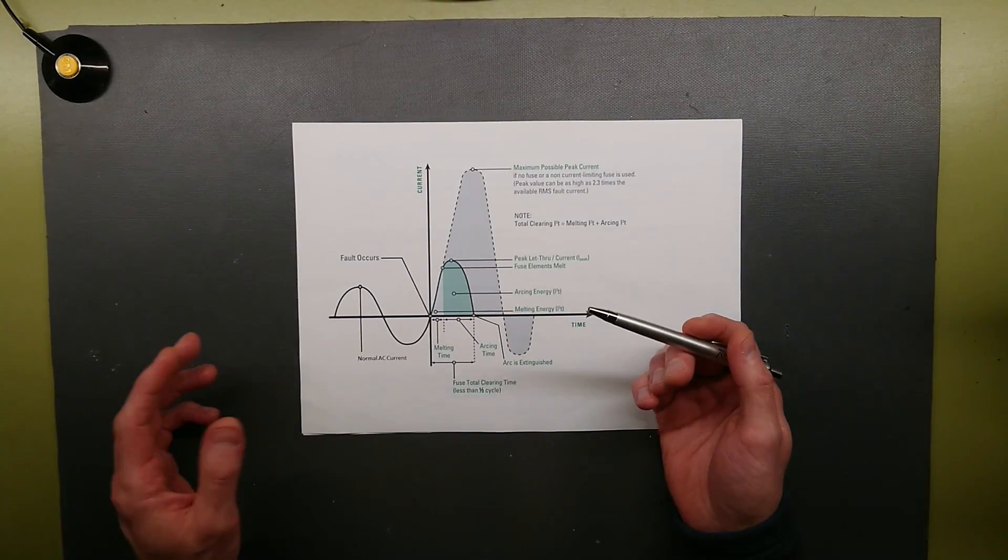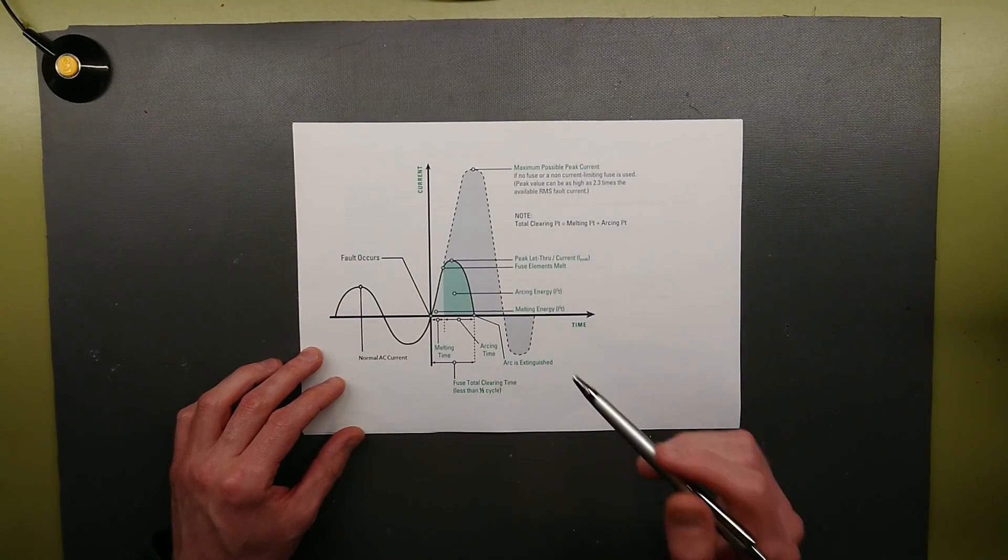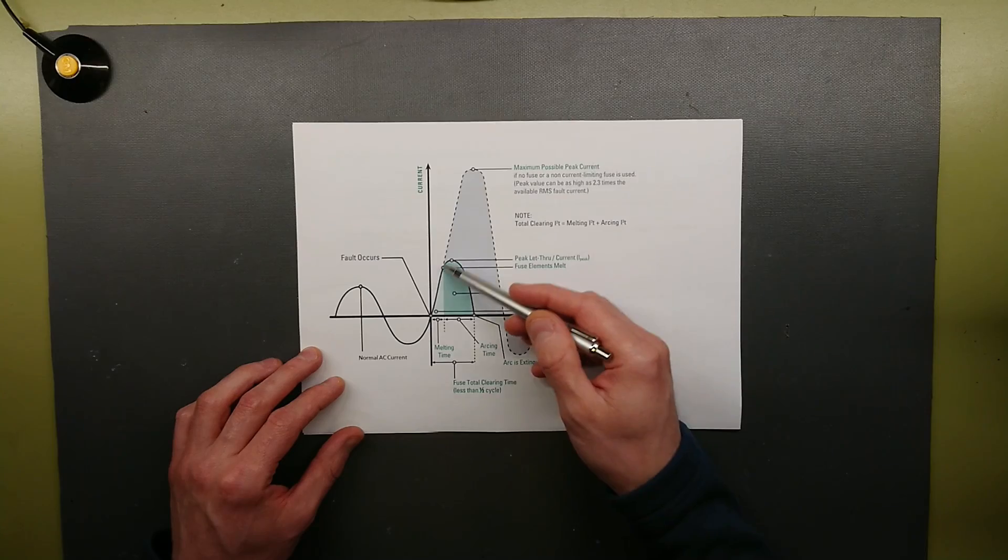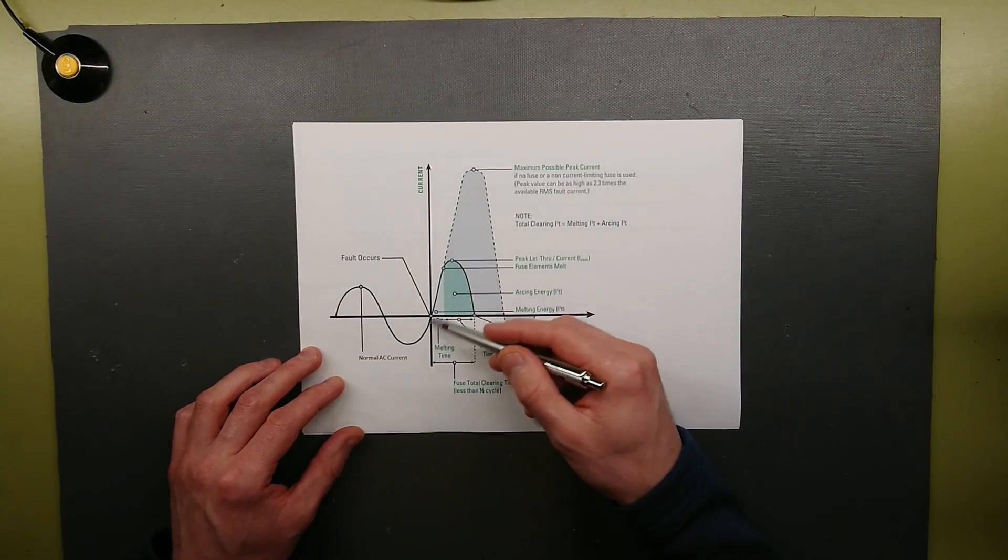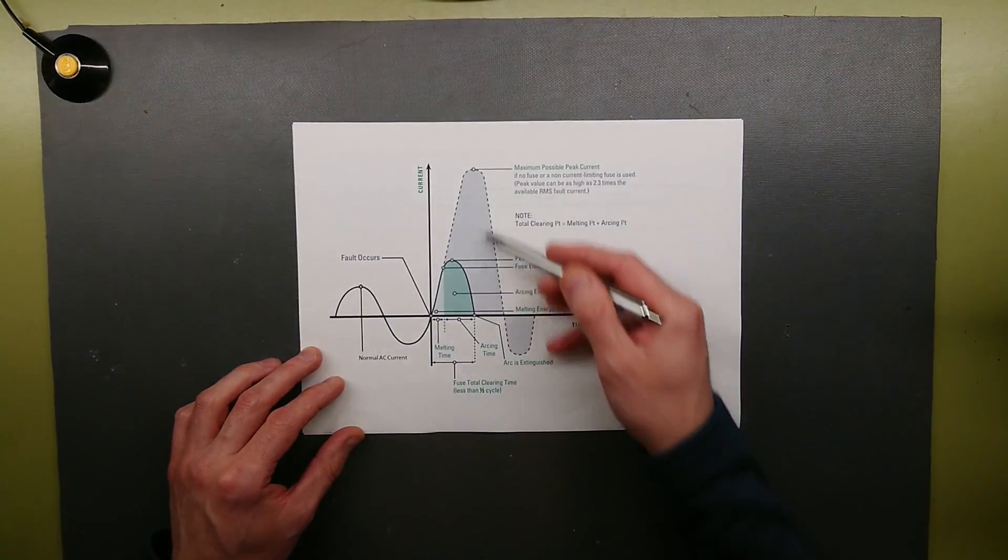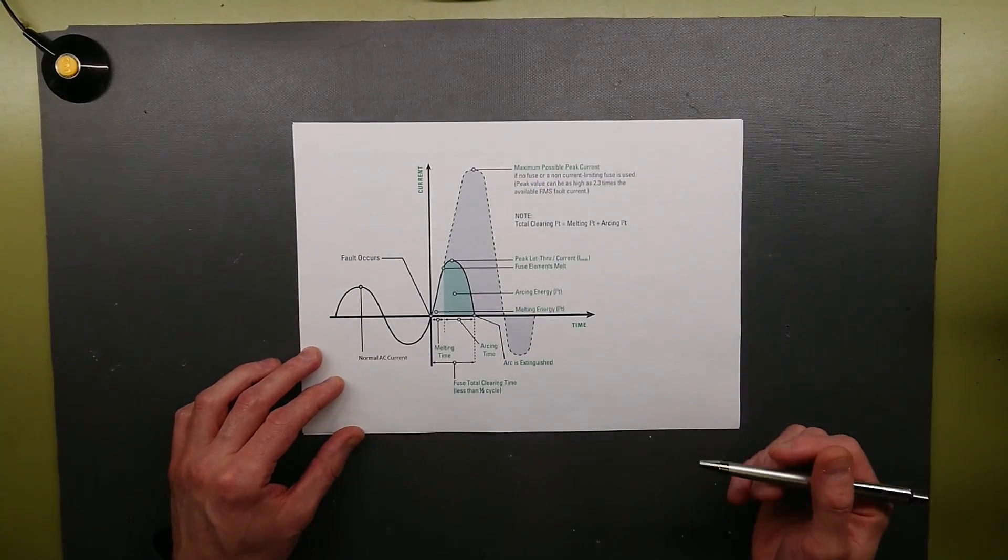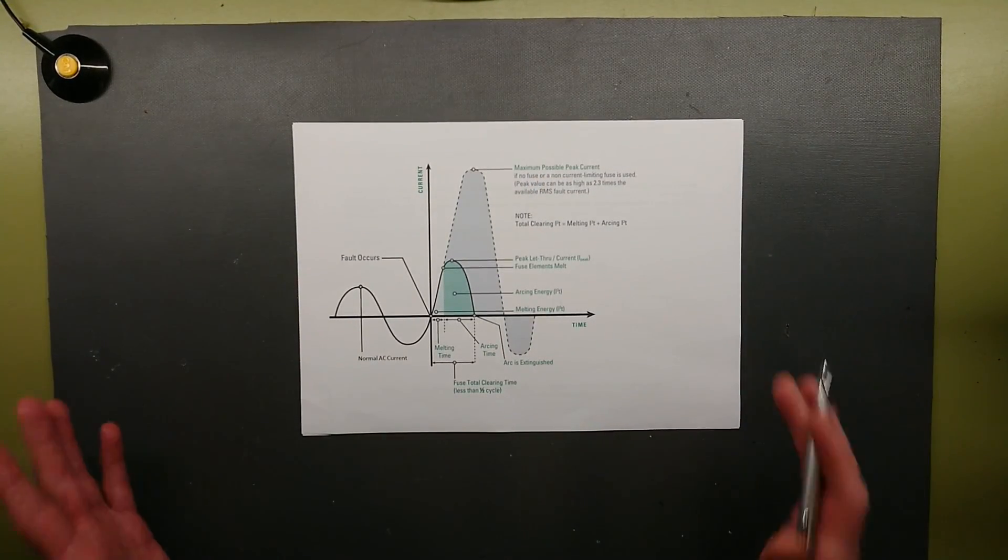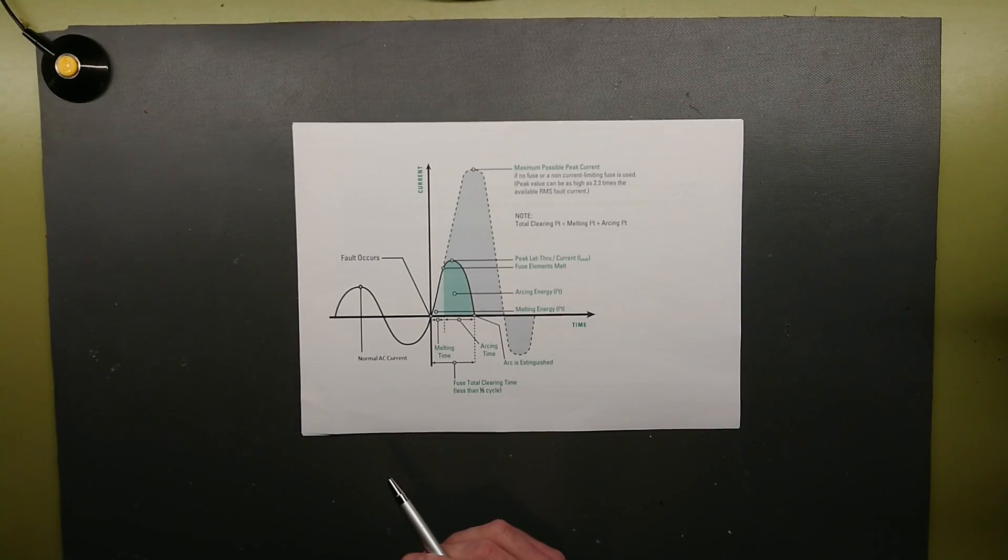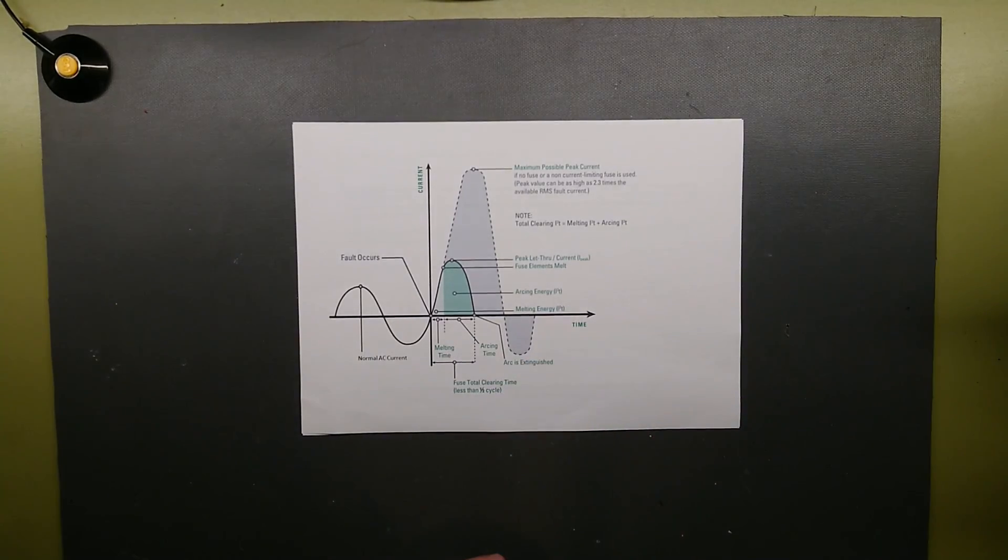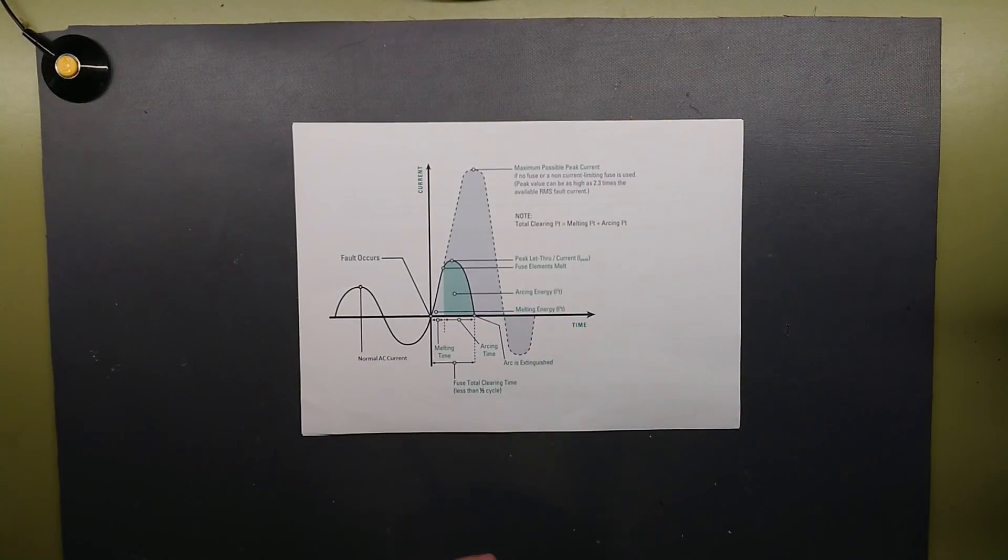This total amount or area under the graph here, that is what is the I2T. The amount of energy over time, amperes squared times seconds. That is how you determine how much energy is let through. The area under this part of the graph is much smaller than the total area. That is actually what I2T is, the amount of integrated energy from the current and time graph.